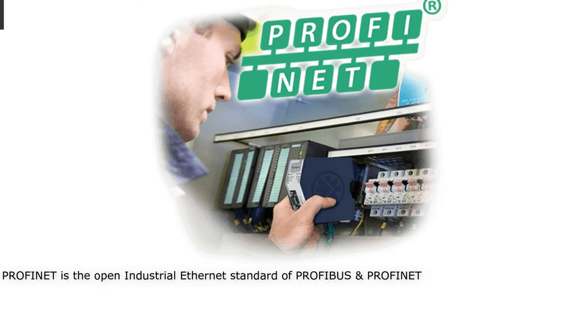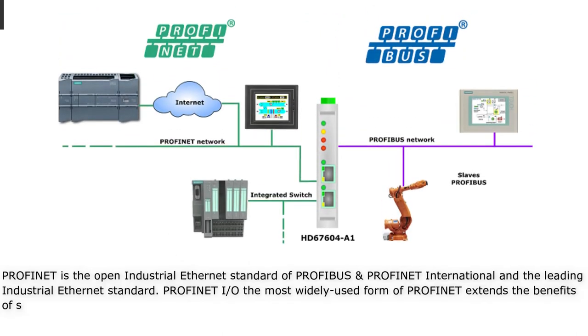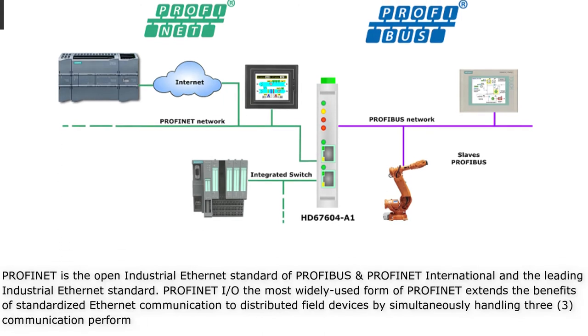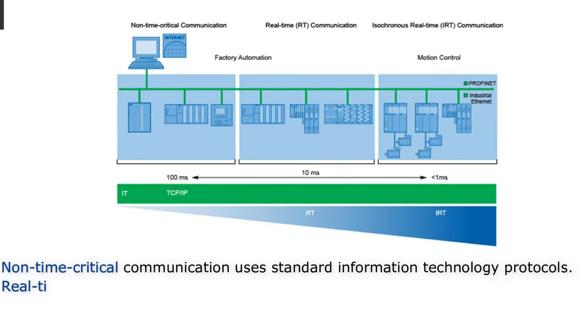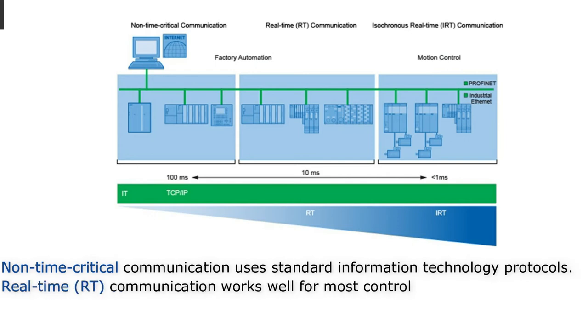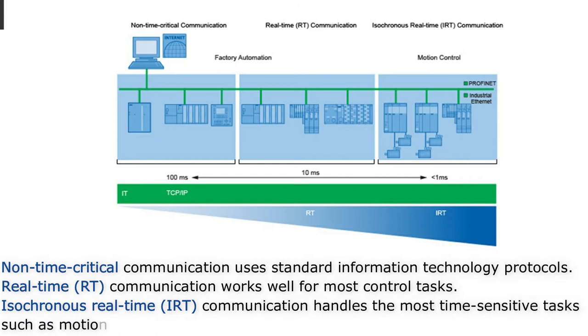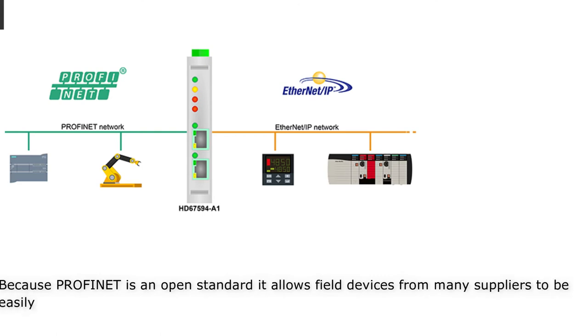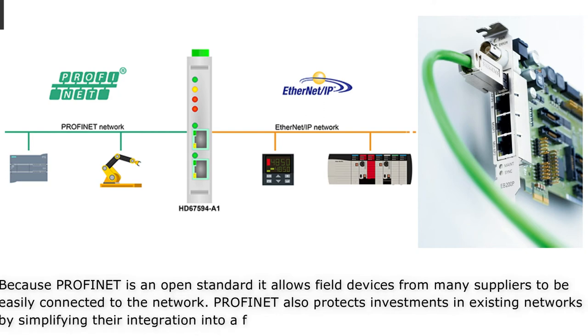Profinet is the open industrial Ethernet standard of Profibus and Profinet International and the leading industrial Ethernet standard. Profinet IO, the most widely used form of Profinet, extends the benefits of standardized Ethernet communication to distributed field devices by simultaneously handling three communication performance levels: non-time-critical communication using standard IT protocols; Real-Time (RT) communication, which works well for most control tasks; and Isochronous Real-Time (IRT) communication, which handles the most time-sensitive tasks such as motion control. Because Profinet is an open standard, it allows field devices from many suppliers to be easily connected, and also protects investments in existing networks by simplifying their integration into a factory-wide network.